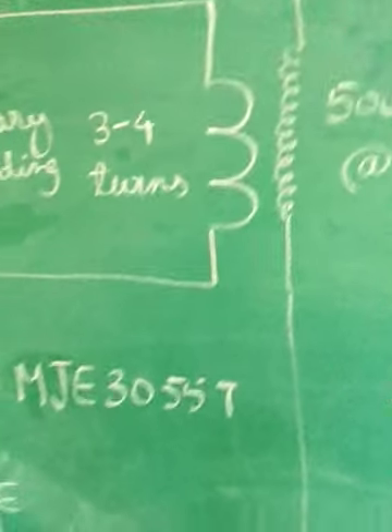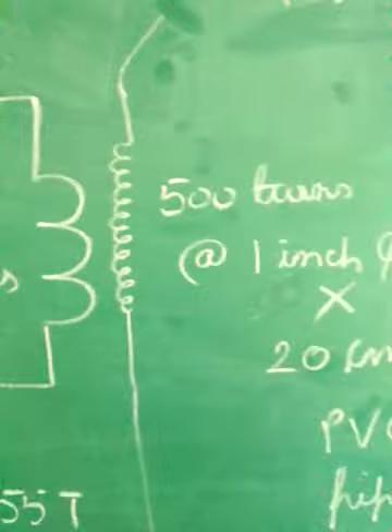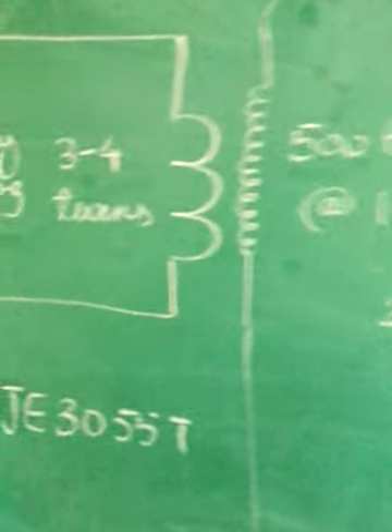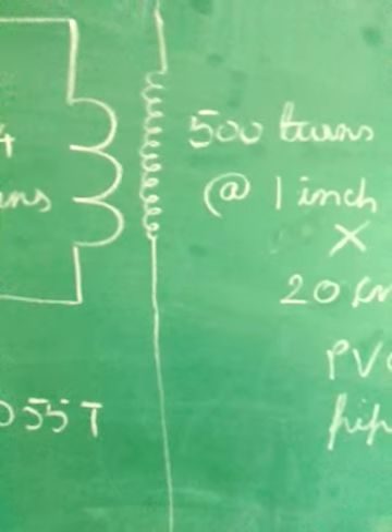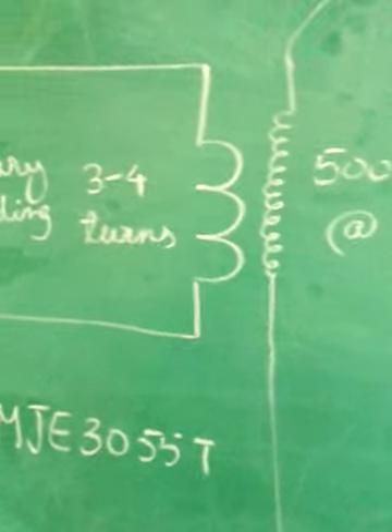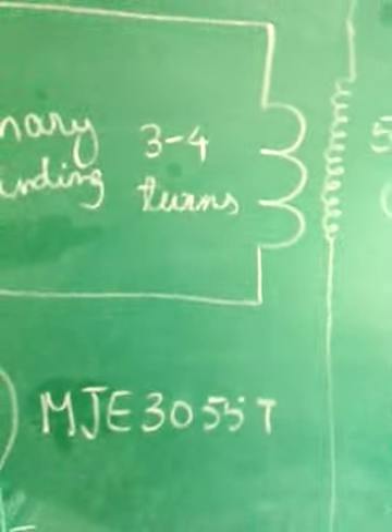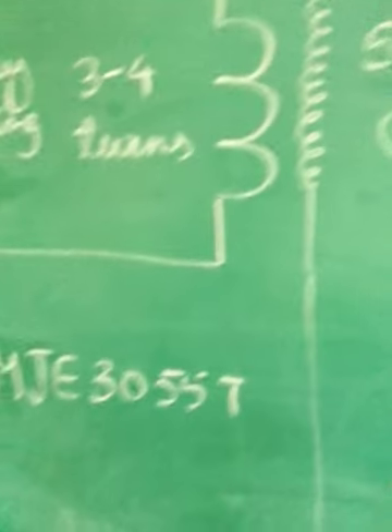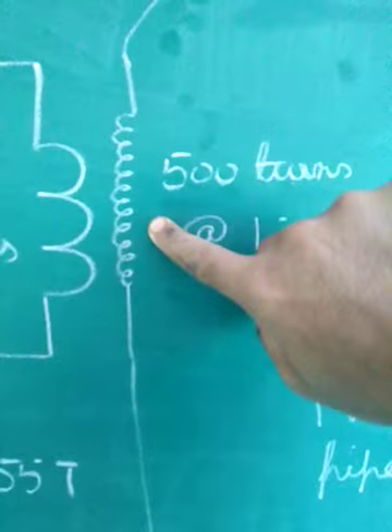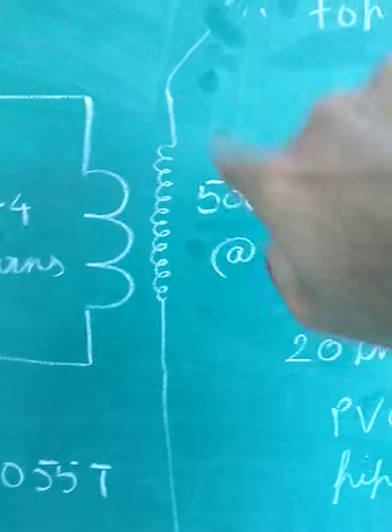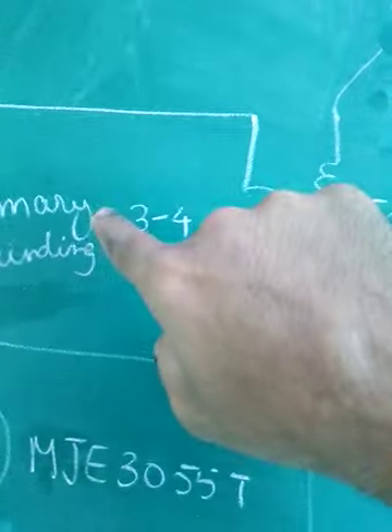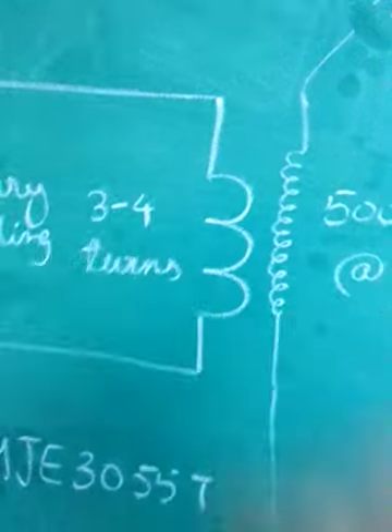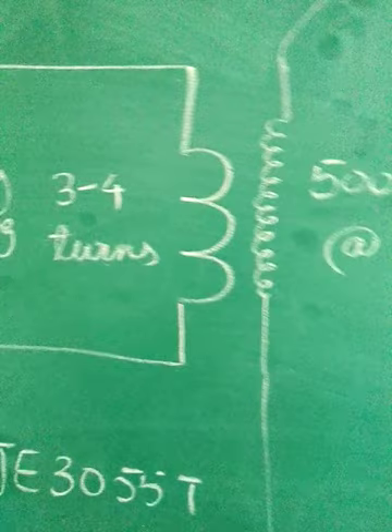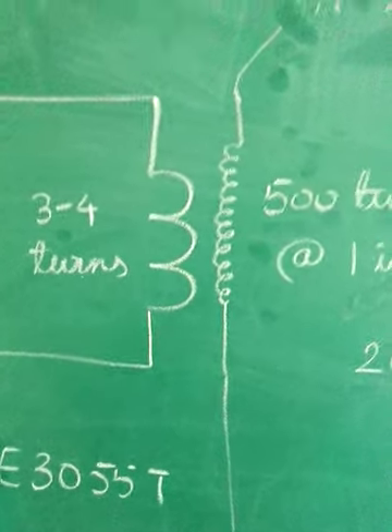An important aspect of the primary and secondary is that the direction of winding has to be opposite to each other. For example, looking down from the top, if your secondary turns clockwise, your primary should turn anti-clockwise. This is because you want additive polarities.